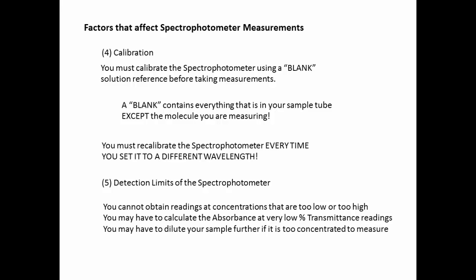You may have to dilute your sample further if it's too concentrated to measure. If you put your sample in and you get 0% transmittance, which will result in infinite absorbance, you can't really use that as a reading. You must dilute the sample down in order to make the reading more visible to you.